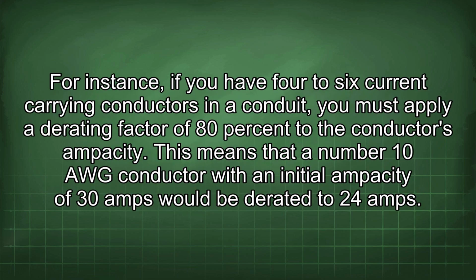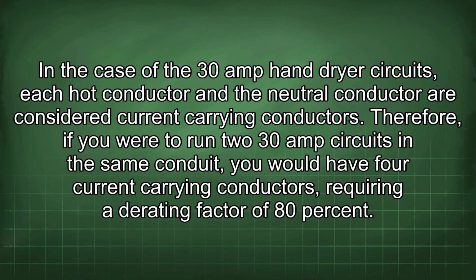For instance, if you have 4 to 6 current-carrying conductors in a conduit, you must apply a derating factor of 80% to the conductor's ampacity. This means that a number 10 AWG conductor with an initial ampacity of 30 amps would be derated to 24 amps. In the case of the 30 amp hand dryer circuits, each hot conductor and the neutral conductor are considered current-carrying conductors. Therefore, if you were to run two 30 amp circuits in the same conduit, you would have 4 current-carrying conductors, requiring a derating factor of 80%.